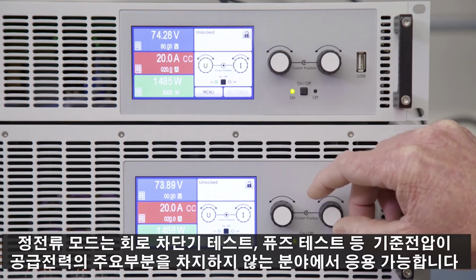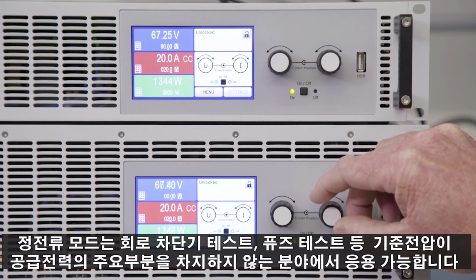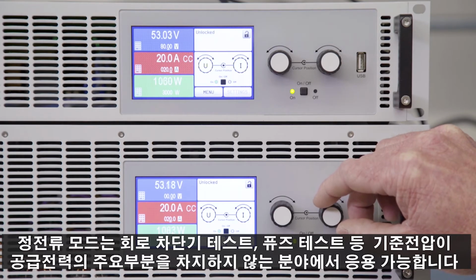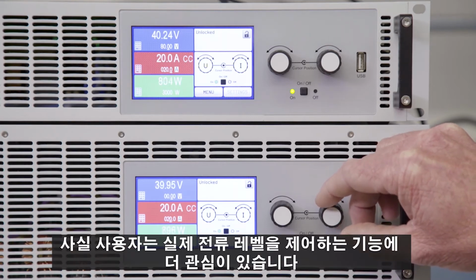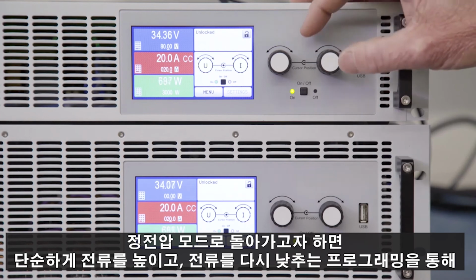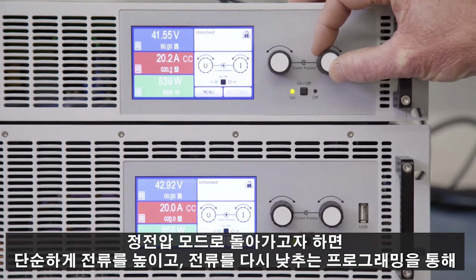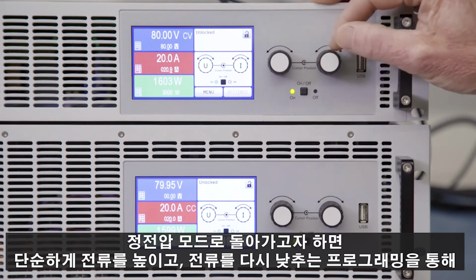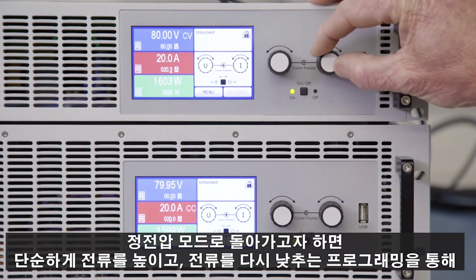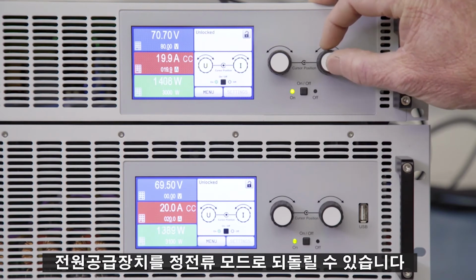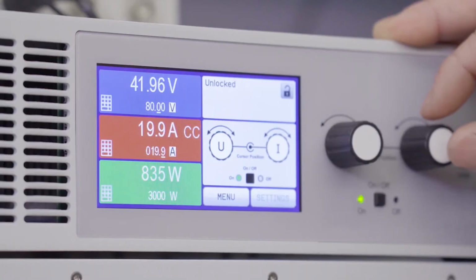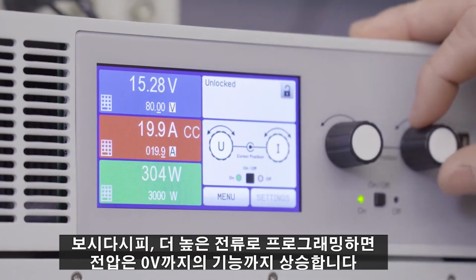Constant current mode can be useful in applications such as circuit breaker testing and fuse testing, where the reference voltage is not necessarily the most important portion of the power that it's delivering, and the users are more interested in controlling the actual current levels. That current, of course, can be adjusted. You can program the current limit. If you actually want to go back into constant voltage mode, simply increase the current up, and then you can also take the current back down to force the power supply back into constant current mode. And as you see, the voltage will ramp down all the way to 0 volts if you program higher currents.